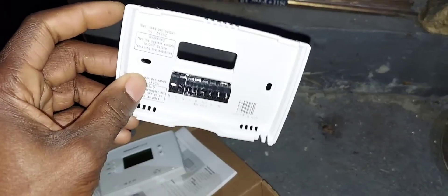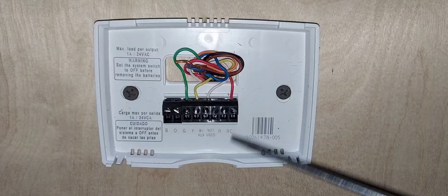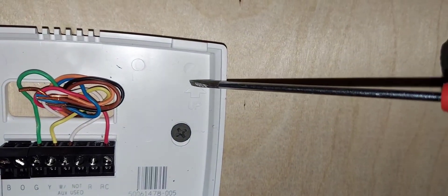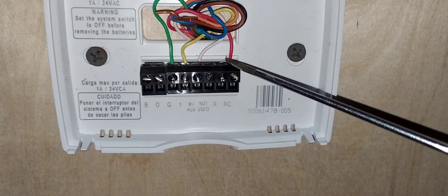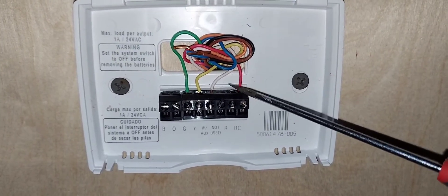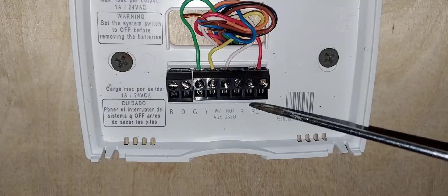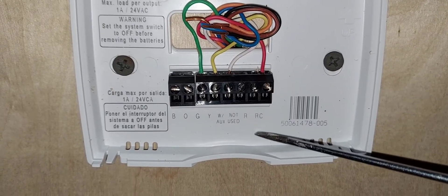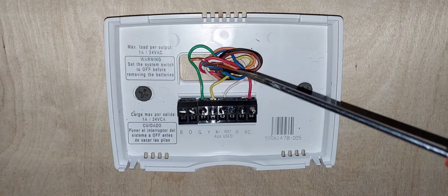Let's install this thermostat. Here we are with the wiring — the sub base is installed. Take note of the arrow pointing up. I have my power landed on RC, which is the red wire. Remember, if your colors are different it doesn't matter — colors are arbitrary. Just make sure the wire connecting to R or RC on the thermostat matches the R or RC terminal in your HVAC equipment.